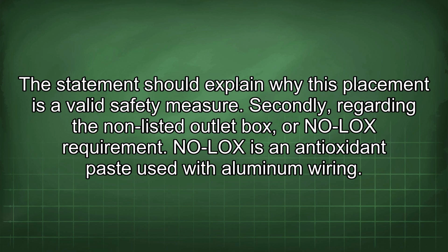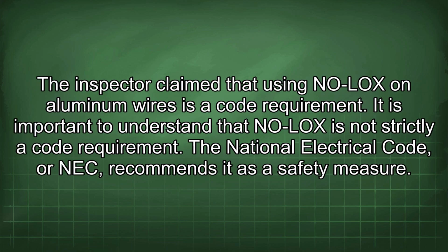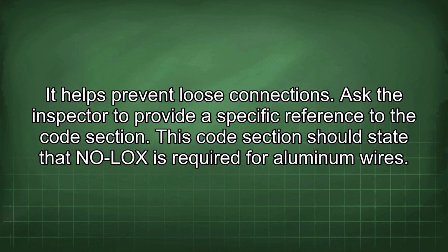Secondly, regarding the non-listed outlet box, or NO-LOX requirement. NO-LOX is an antioxidant paste used with aluminum wiring. The inspector claimed that using NO-LOX on aluminum wires is a code requirement. It is important to understand that NO-LOX is not strictly a code requirement. The National Electrical Code, or NEC, recommends it as a safety measure. It helps prevent loose connections.